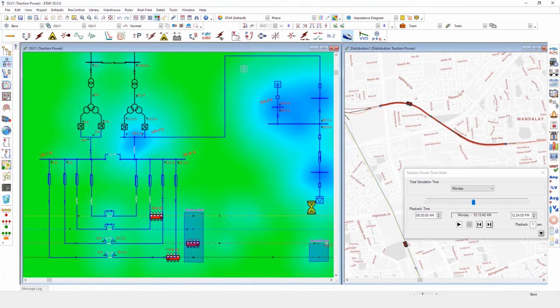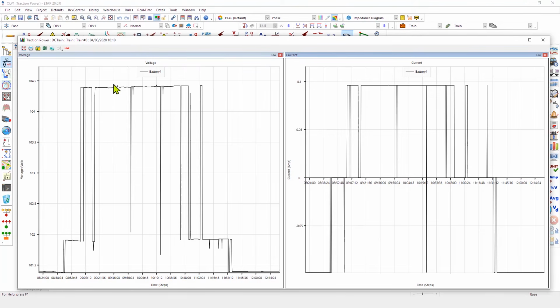You can also plot all of this information just like time domain load flow as a function of time and observe the behavior of the battery voltage and current as it goes through various transitions of charging, no charge, and discharge in the system, and how it's able to maintain the terminal voltage at the battery terminals or the substation terminal buses as well.